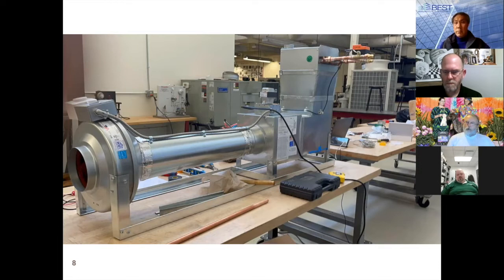I've got my elbow up there, my piping, and my 3-way valve and actuator on top. What you can't see is there's a hot water heater in our lab, about 15 feet away. We moved this table closer to the hot water heater and connected it, running water through the coil, so you could see the discharge temperature rise as the three-way valve opened up and allowed flow through the coil instead of bypassing it.